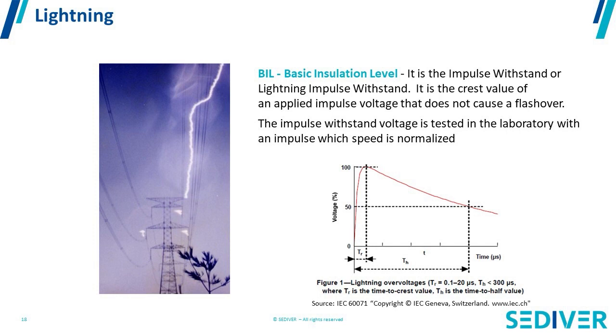Starting with lightning — you don't control a thunderstorm. Lightning will come in and touch a line in very strange ways. On the picture, there is a lightning actually touching the shield wire, in direct contact with the ground value of the tower itself. It's very interesting to see that all three insulator strings have a flashover. This is because when lightning hits the tower, the voltage of the entire tower goes to very high values, higher than the voltage of the line, and you actually have a flashover going from the tower to the conductor. This is what we call a back flashover.